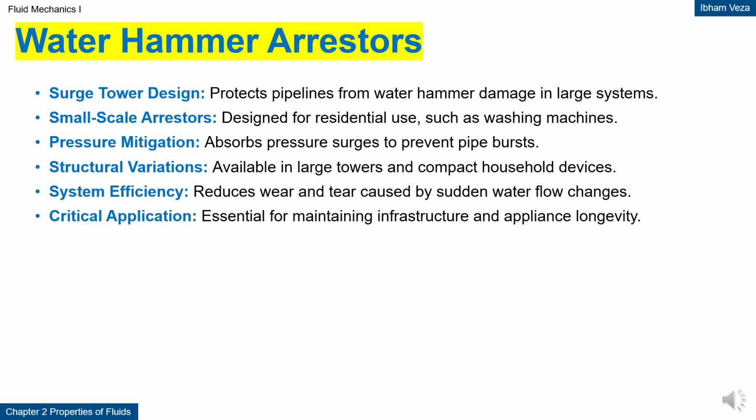Surge towers and small arrestors are designed to absorb these pressure spikes. With these devices, the temporary pressure energy can be safely dissipated. This protects pipes, valves, and equipment from damage. This concept shows the importance of considering transient effects in fluid system design.